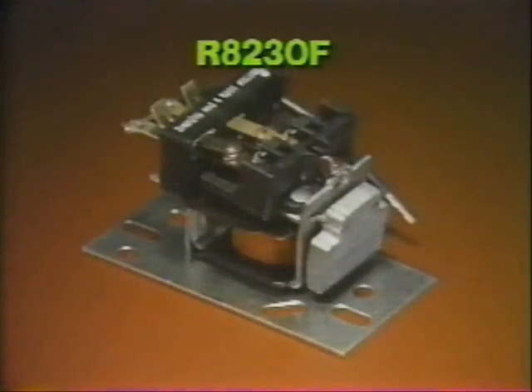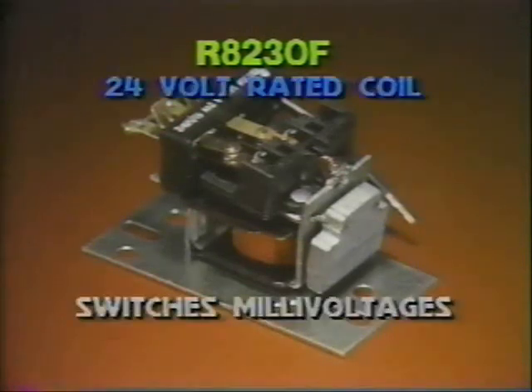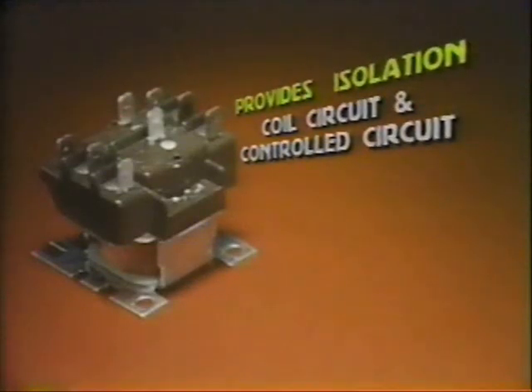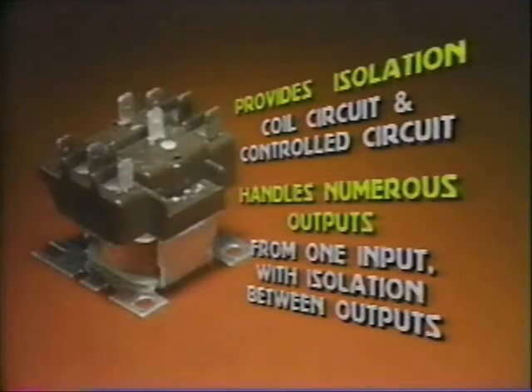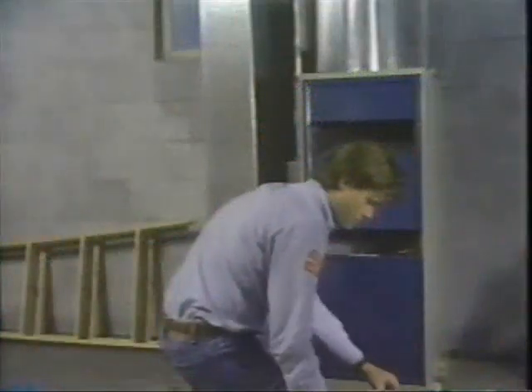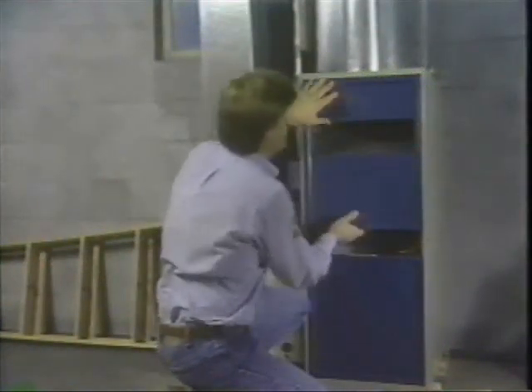A relay with properly rated contacts can also switch circuits with lower voltages than the control circuit. For example, a 24-volt thermostat circuit controlling a millivoltage gas valve. Relays have two other very important characteristics. First, they provide electrical isolation between the control circuit, the coil side, and the circuit being controlled, the contact side. Second, a relay can control a number of outputs from a single input, and these outputs can be isolated from each other electrically.